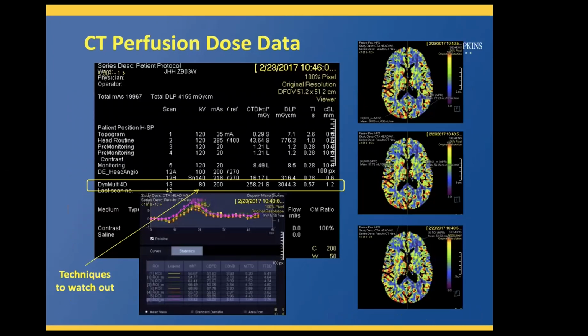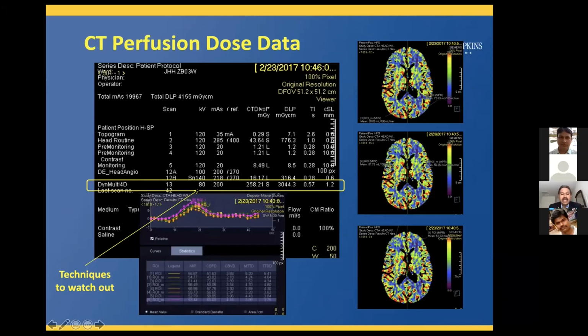And here is the effective dose estimation. It is also important if the clinic is doing CT perfusion, where the CT perfusion part has to be done at a lower kVp, at 80 kV. Otherwise, the radiation dose can be really high, leading to hair loss or skin burns. So it's important that the protocols are done at a lower kV.